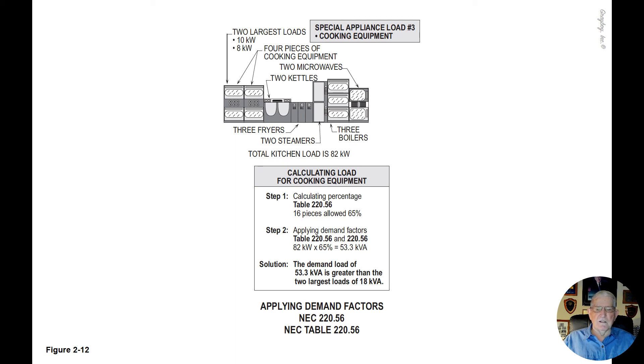Figure 2-12 illustrates how to apply a demand factor for cooking equipment used in a commercial or industrial location based on the number of units present. Essentially, about 65% of that load would be used at one time, because you turn the heat up on the cooking equipment to get it going, then reduce the setting to cook without burning the food. So based on the number of units, you get a percentage listed in Table 220.56 — that's what this figure is illustrating.